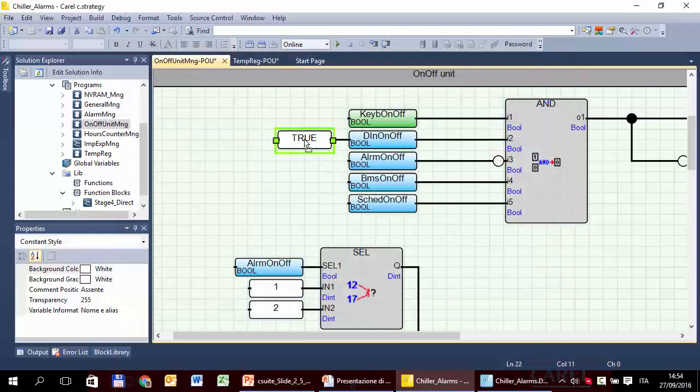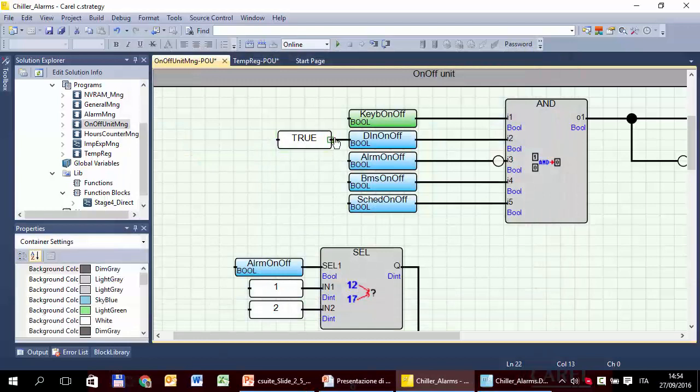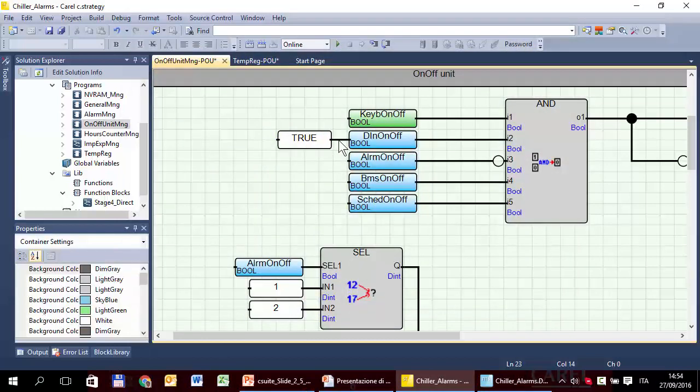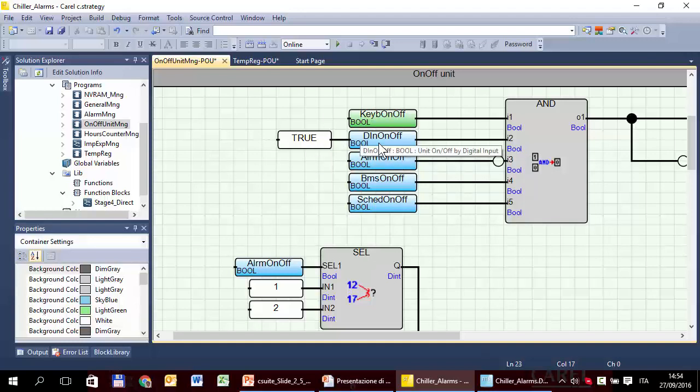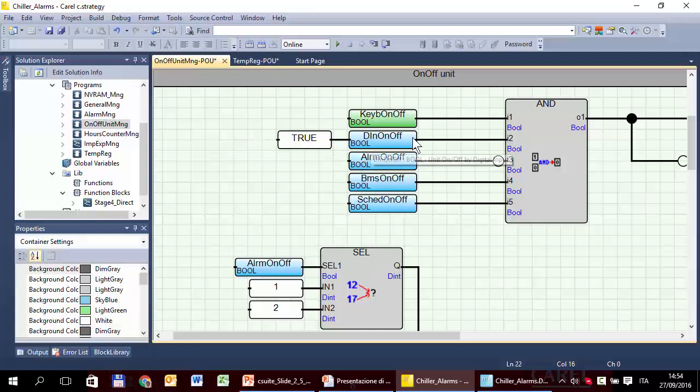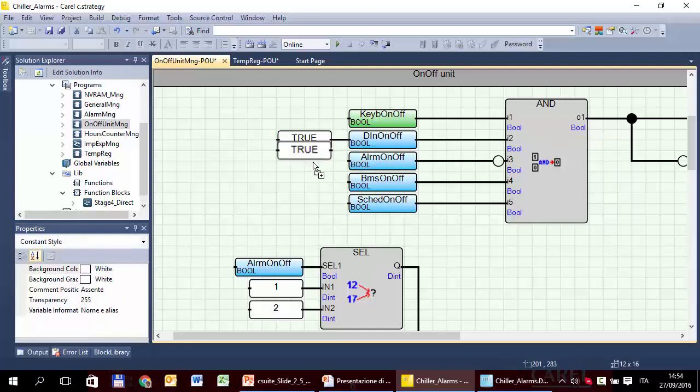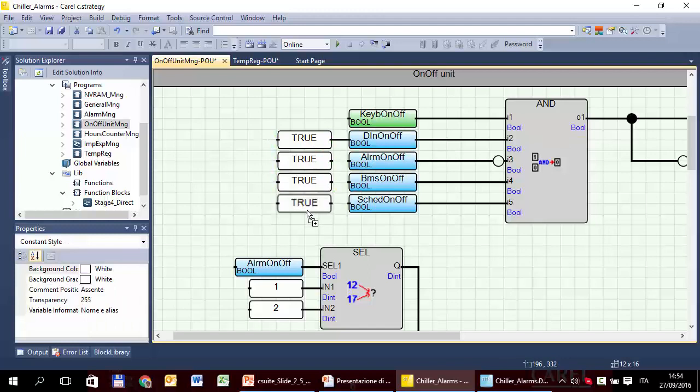In my opinion, the fastest way to fix the problem is simply force these values to a value corresponding to unit is on. So we can add a variable, the value is true, like this. If remember, a straight connection between a constant or a variable to a variable corresponds to a move, that is, this value is copied inside this variable. So, run time, the digital input on-off will take the value true, so that it won't have effect in the AND block.